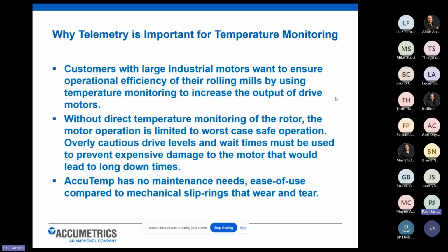So the AccuTemp system that we have, again, has no maintenance needs. It's very easy to use. It eliminates the issue of any kind of mechanical slip rings that would wear and tear over time. It gives you that direct access to temperature inside of your motor.